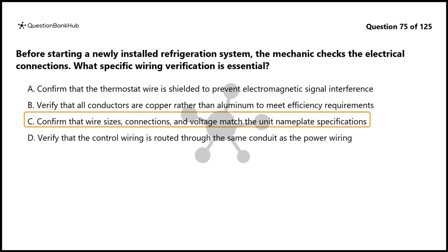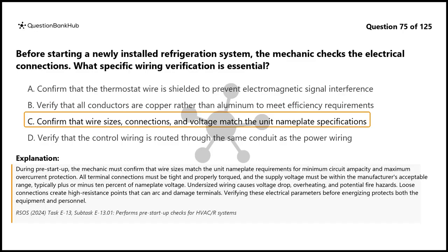The correct answer is C. During pre-startup, the mechanic must confirm that wire sizes match the unit nameplate requirements for minimum circuit ampacity and maximum overcurrent protection. All terminal connections must be tight and properly torqued, and the supply voltage must be within the manufacturer's acceptable range, typically plus or minus 10% of nameplate voltage. Undersized wiring causes voltage drop, overheating, and potential fire hazards. Loose connections create high resistance points that can arc and damage terminals. Verifying these electrical parameters before energizing protects both the equipment and personnel.